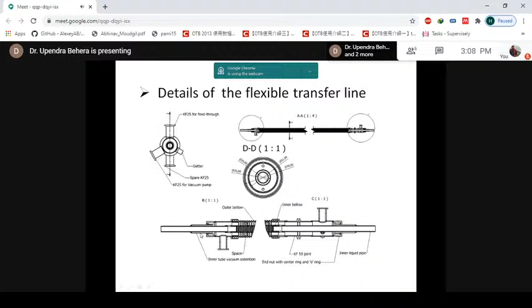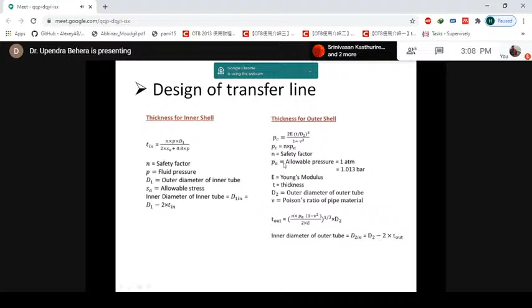We have done the calculation for the thickness of this inner bellow and outer bellow based on the same equations given by the ASME pressure vessel code Section 8, which I have already explained. The pressure drop for single phase and two phase flow we have also considered. For single phase flow, the pressure drop over unit length, delta P by delta L, is given by this equation: f, the friction coefficient, into mass flow rate by cross sectional area squared, 1 by 2 g_c rho, into d_in, where d_in is the inner tube diameter.